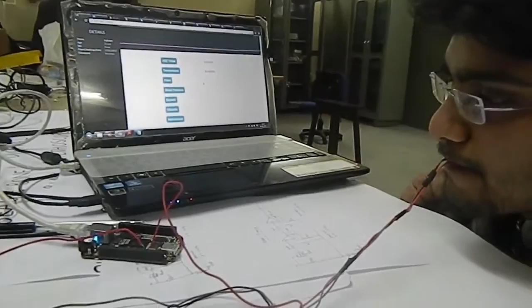This is a temperature measurement circuit. As you can see, the patient has inserted the probe into his mouth. The probe contains the temperature sensor. And now, as you can see, against the temperature tab that is being shown on the server has Fahrenheit values, and it has started to increase as the temperature level has shifted from the atmospheric temperature to the body level temperature. The temperature that is being shown over here is in Fahrenheit. Since the temperature is coming around 100 degree Fahrenheit, we come to a conclusion that it is in close measure with the accurate temperature.